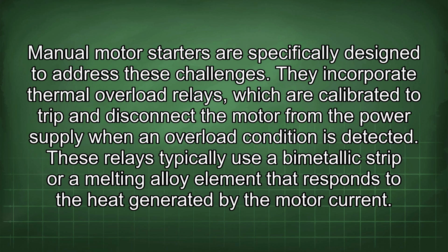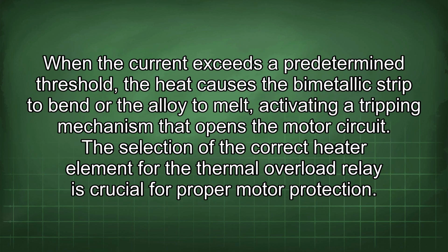Manual motor starters are specifically designed to address these challenges. They incorporate thermal overload relays, which are calibrated to trip and disconnect the motor from the power supply when an overload condition is detected. These relays typically use a bimetallic strip or a melting alloy element that responds to the heat generated by the motor current. When the current exceeds a predetermined threshold, the heat causes the bimetallic strip to bend or the alloy to melt, activating a tripping mechanism that opens the motor circuit.